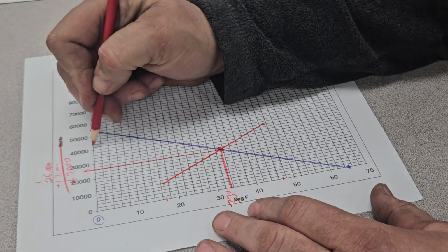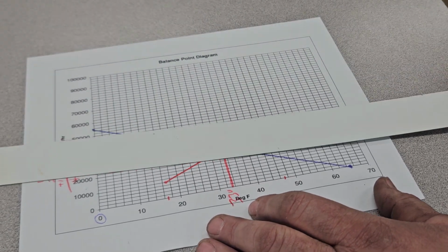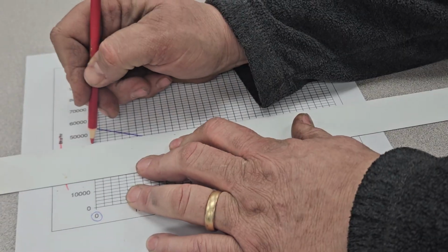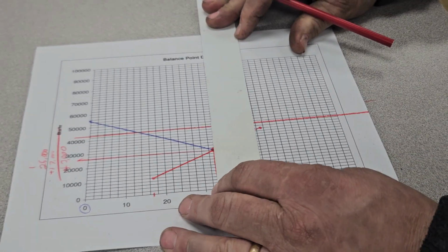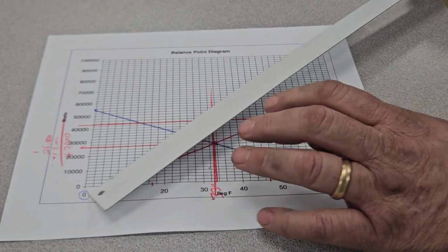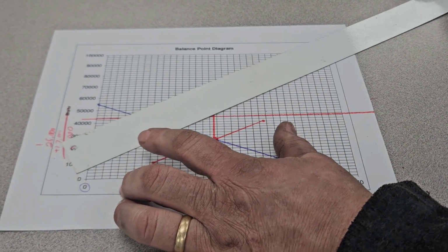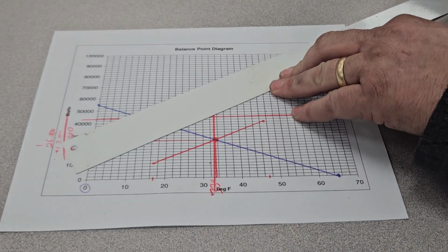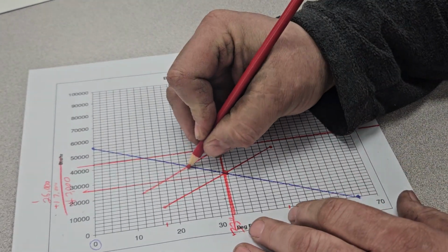43,000 BTUs. So we'd come up to the 43,000 BTU mark, and I would draw a line straight across for that. Okay, let me draw a line up. And then I want to use the same angle as the heat pump. I want to try to get it as best I can, the same angle as the heat pump, where those 2 marks meet. And I'm going to consider this to be my new balance point on this diagram.